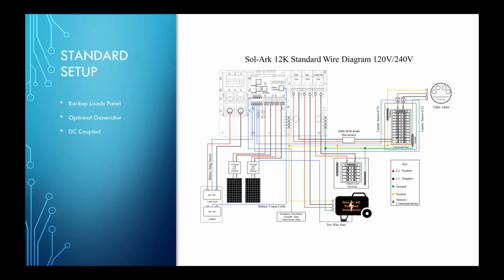So it does kind of break down into a critical loads panel. You have your generator connections, just as David was talking about. Just keep in mind as you are making your interconnections or connecting to any type of main service panel, make sure to follow the rules and regulations, which differ. A lot of the times the previous models were 50 amp breakers for the grid and load. Those have been extended up to 63 amps. So a 60 amp breaker, if my calculations still serve me correctly, won't be able to fit inside a 200 amp panel without derating or any of that nature. But nevertheless, we do recommend a 60 amp for there, and then the critical loads panel and generator connections are pretty standard. Then again, in the middle section, you have your MPPTs for the panels and your battery connections on the left.